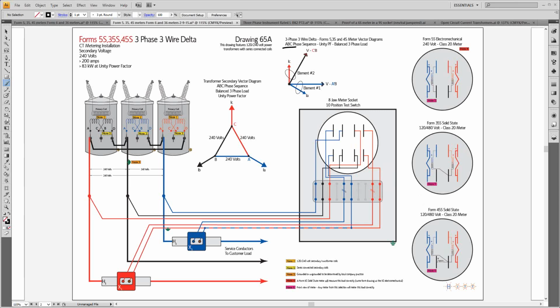Question for you: do you still have a lot of your downtown stuff as deltas like we do in Utah? In Seattle? Yeah, there's lots of stuff. Not right in downtown. Right in downtown, not as much of that, but from about where the stadiums are going south from there, lots of delta in that area. Mostly 4-wire delta, not a lot of 3-wire delta in our system, but mostly still lots of delta out there, lots of open delta banks, and most of them are wired with 2 CTs, that type of thing, and that's what we're going to talk about next. We still have a lot of our stuff downtown. I still run into 3-wire deltas on some of the really old stuff. Do you? Yeah.